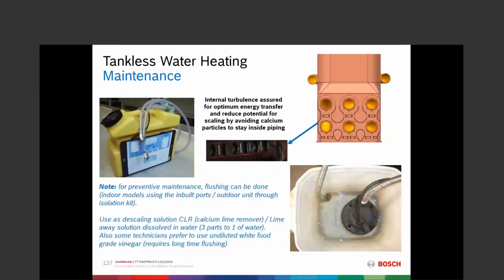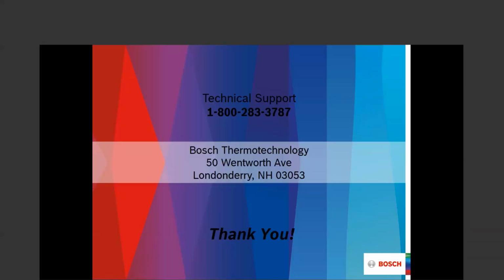Then after sales descaling, very simple. Again, we have those at the bottom. We have our service ports. So we're just going to take our transfer pump, washing machine connectors, and flush that thing out on an as needed basis. And again, we can check for that by looking at that stack temperature leaving the combustion chamber. Typically, we talk about white vinegar as our optimal solution for descaling, but there are certainly other options if you'd like. And with that, thank you so much.